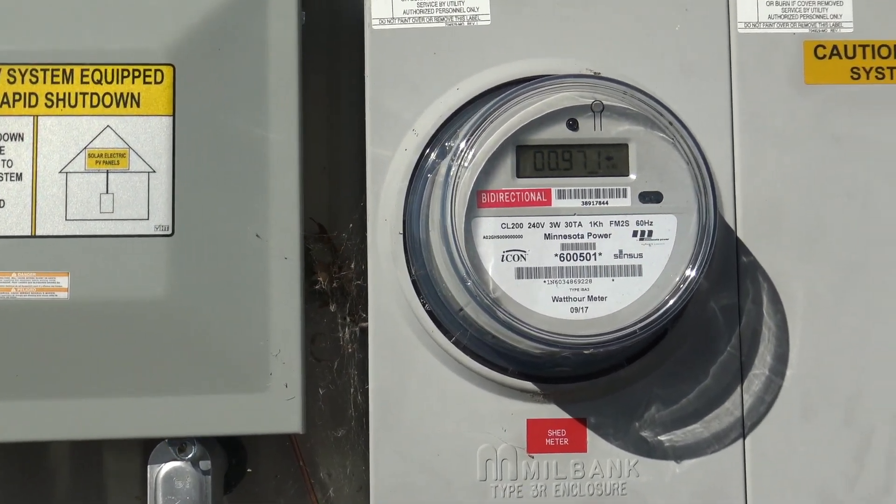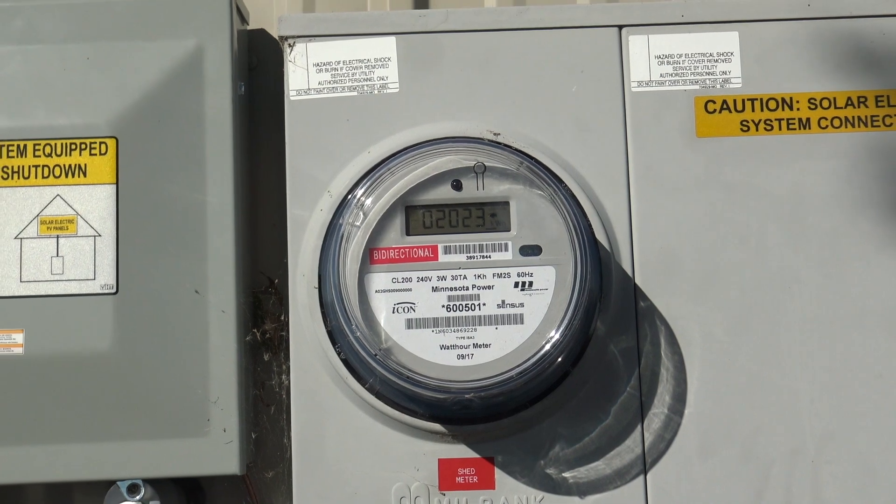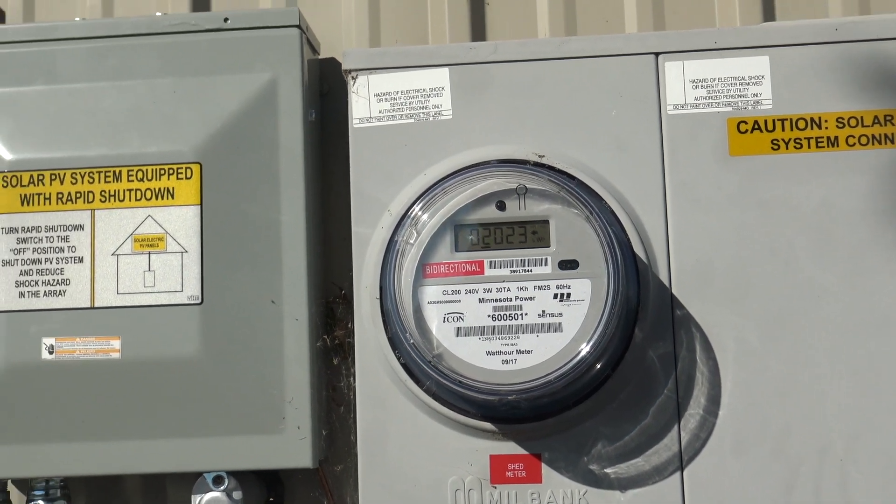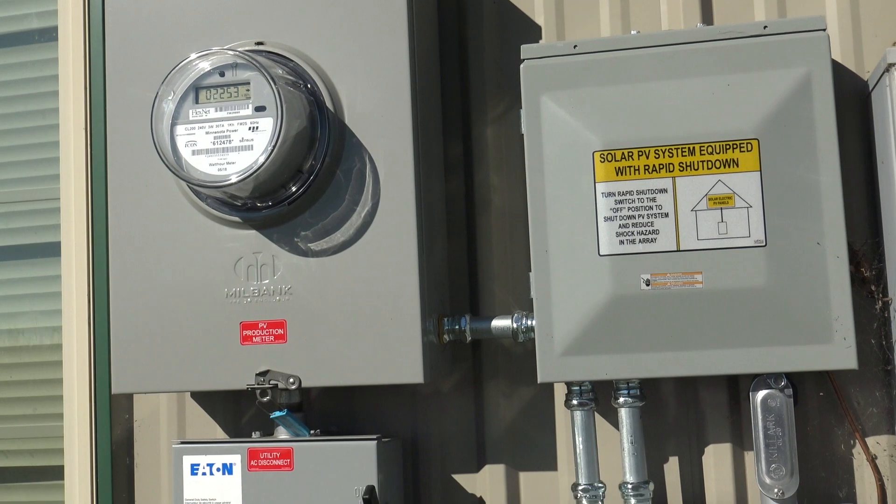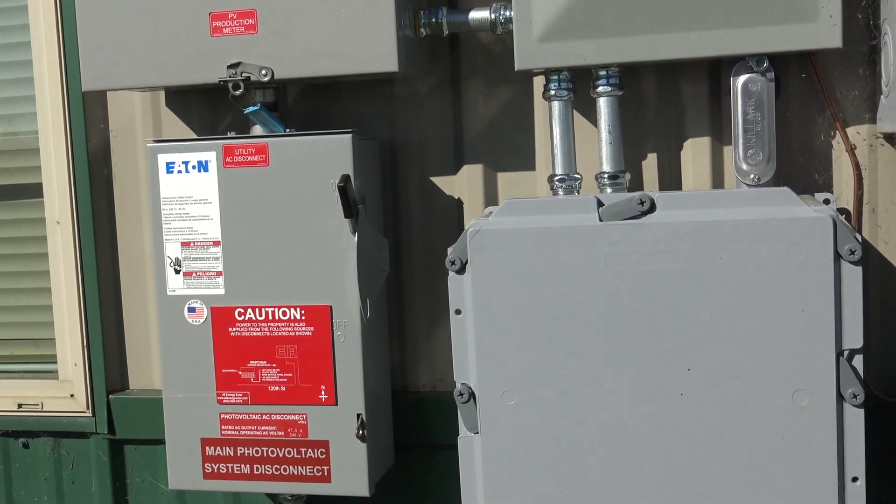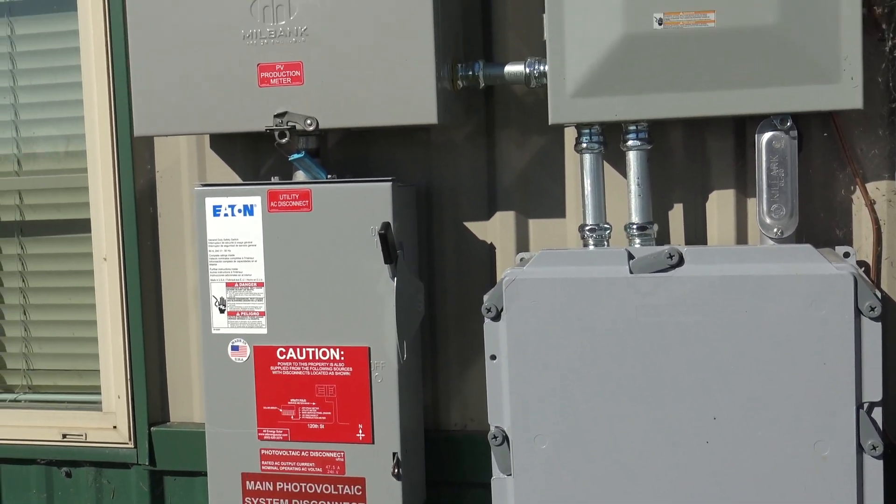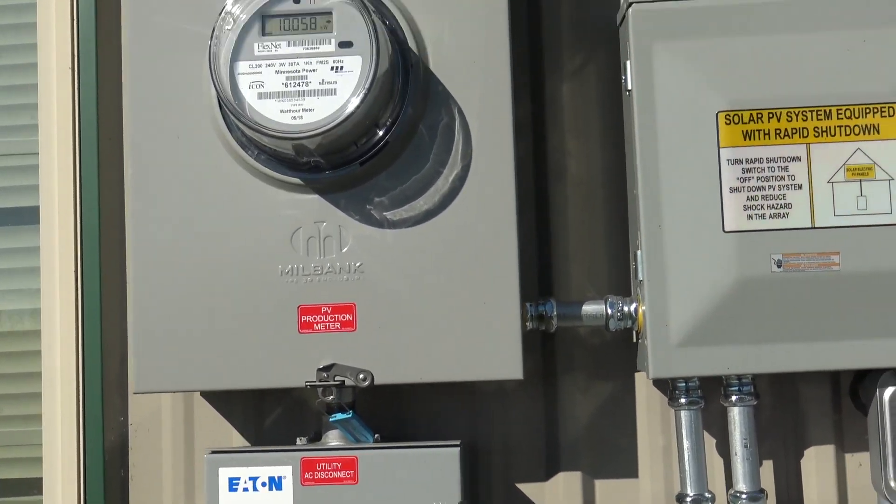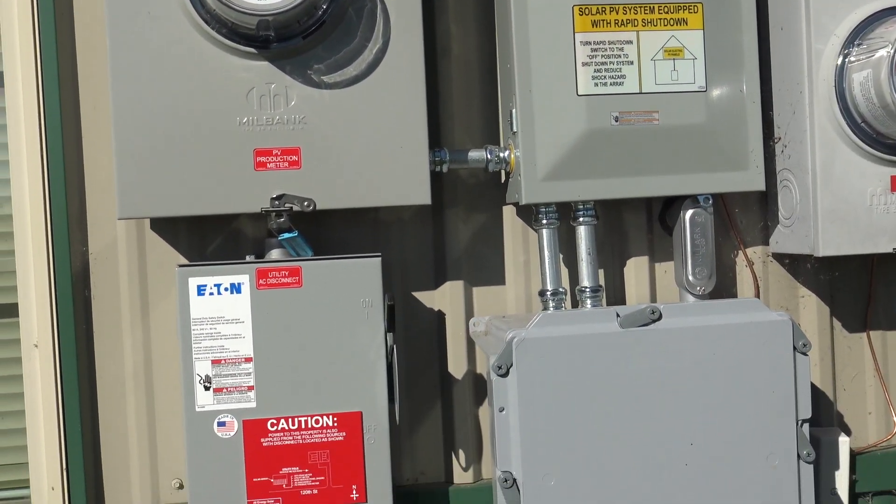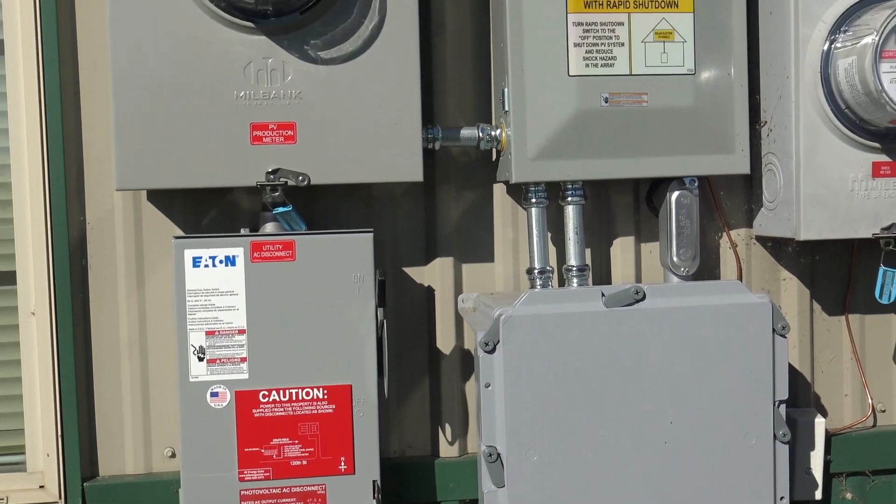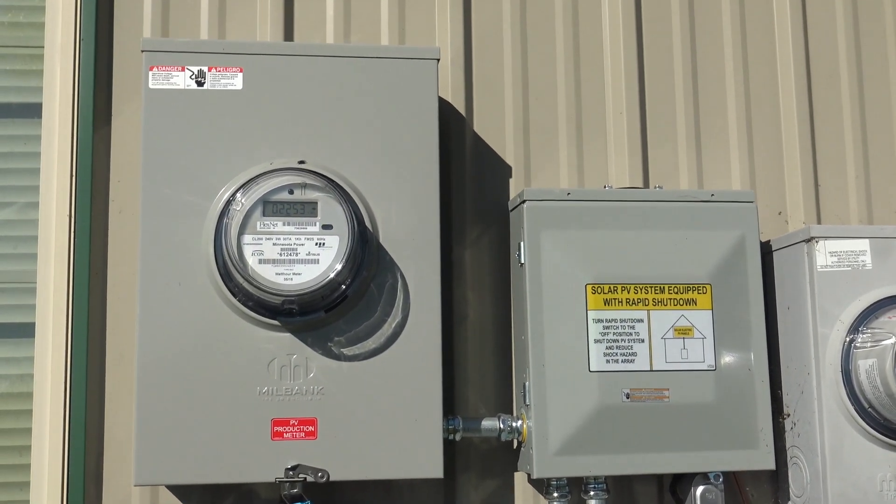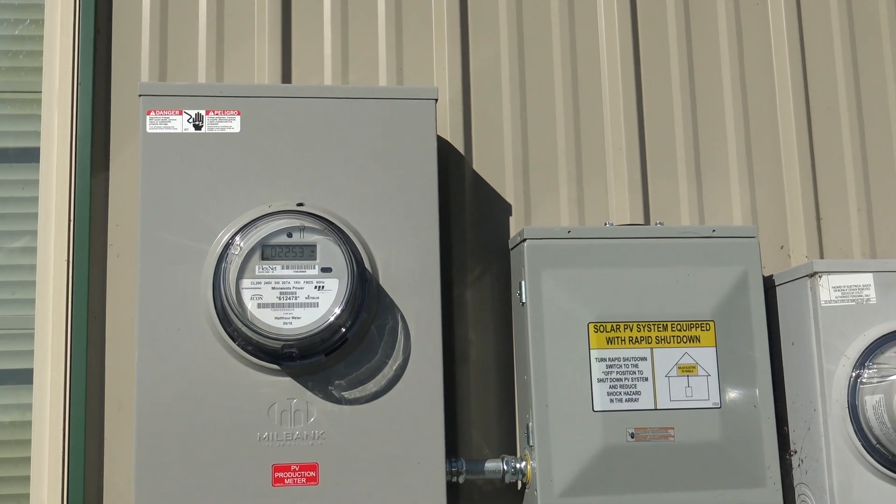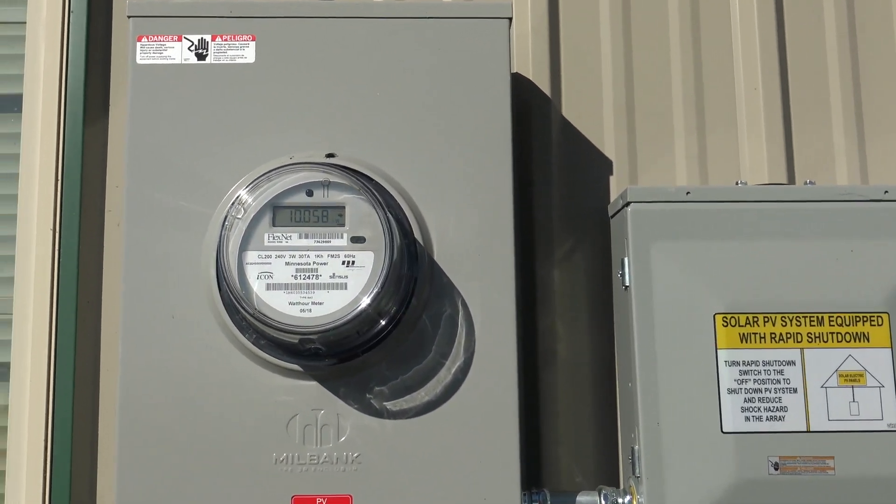This one is a bi-directional meter, meaning that this will go forward or backward depending upon what's happening and how much electricity is being used in the system. Then we have our different cutoffs and connections and such that are going in here. In this particular box, I believe there's some breakers and things that are in this one. There's a main shutoff. And all of this is something that will automatically shut off if the power coming from the power company is off. If it doesn't detect 220 volts coming back, this will shut itself off so it will not produce electricity and give somebody a nasty shock.